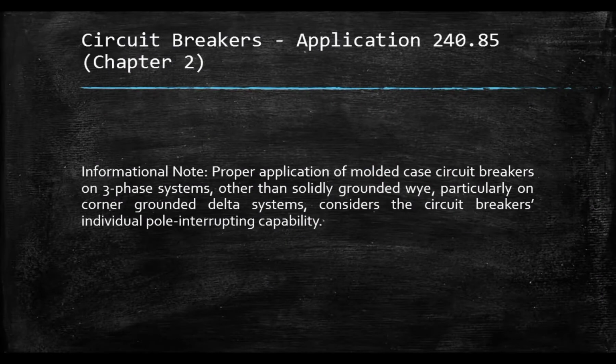Informational note: proper application of molded case circuit breakers on 3-phase systems other than solidly grounded Y, particularly on corner grounded delta systems, considers the circuit breaker's individual pole interrupting capability.